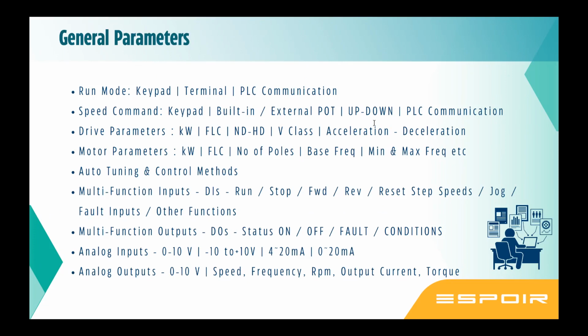There is a built-in pot. If the built-in options are not there, you can use an external potentiometer. Again, you need to be very clear about which point to connect. By wrong connections, you can damage the control card. So you have to be very careful using that external pot. Which terminal, what wire to be connected, you should be very careful. There is another feature called up down. Two push buttons are given. If you constantly press up, the speed goes up. If you constantly press the down key, it reduces the speed. So this feature is also available in certain applications. You can configure it.